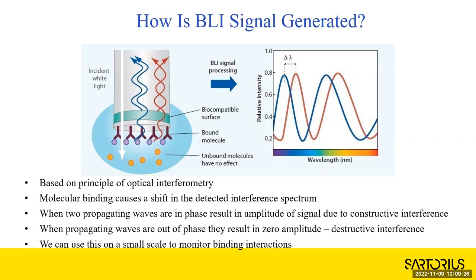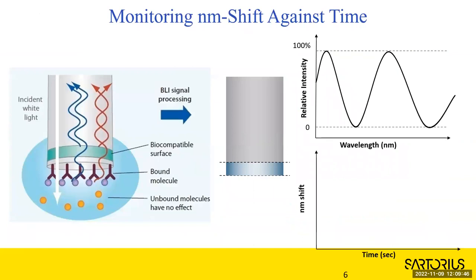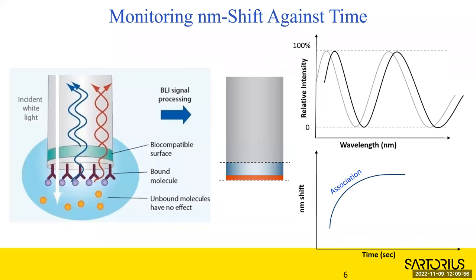Part of the light continues through, and when something binds to the biosensor, the returning wavelength shifts based on how large the molecule is, how much of the molecule there is, and how fast it binds. What you're really looking at is the wavelength shift. In a quick animation: when the biosensor dips into a well, you can watch molecules binding - the signal shift increases during association - then you can move it to a buffer well and watch the return to baseline wavelength during dissociation.